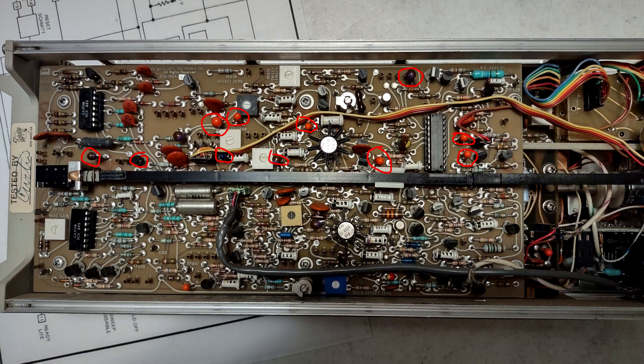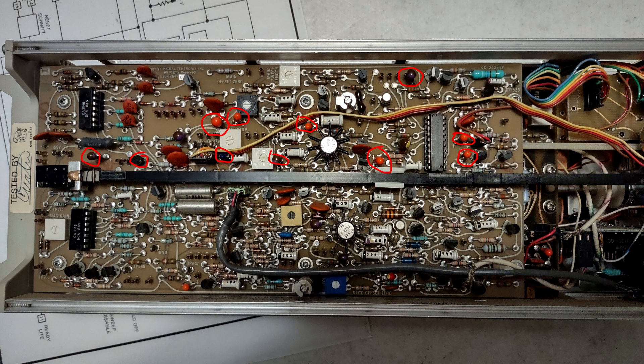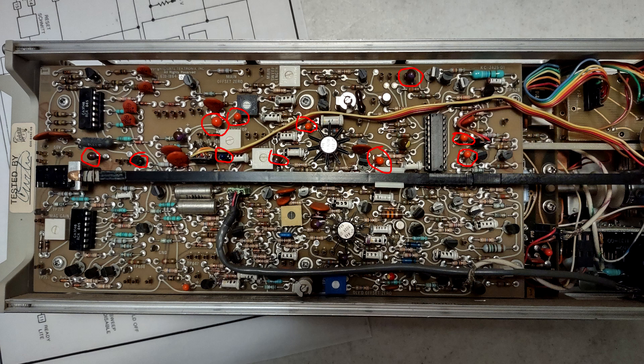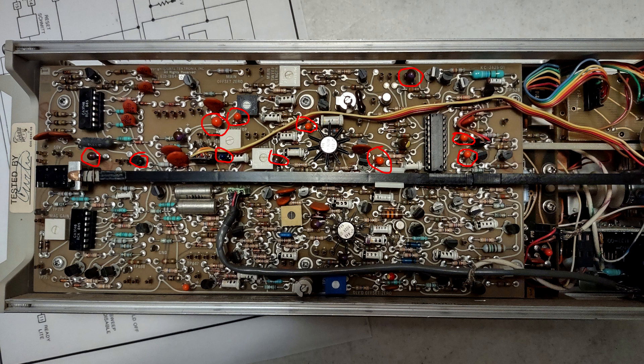Tantalum capacitors are a common failure, so these must be ruled out first. The symptoms of tantalum failure are shutdowns of the mainframe power supply or burned series decoupling resistors or inductors. The plug-in did not affect the mainframe power, and a visual inspection revealed no burned resistors or inductors. There are many tantalums in this plug-in, but it took only a few minutes to probe each one with an ohmmeter, and no failures were found.